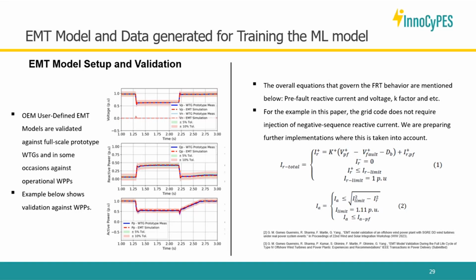But in actual faults, you don't get these flat responses because the fault is very fast and clears quickly. So you can't easily tell visually, or calculate easily, whether the turbine's response was compliant with the grid codes - and that's why we need EMT models.